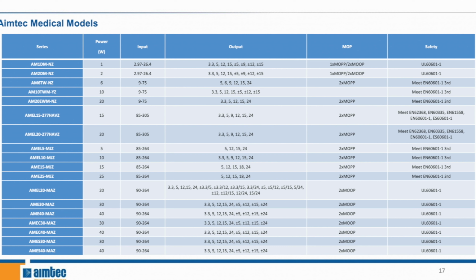And just as a quick note, here is a list of the Aimtec Medical Series. We go from 1 to 20 watts in the DC-DC category, and from 5 to 40 watts in the AC-DC category. And again, it's important to look at the means of protection column to determine whether or not it's MOPP or MOOP. And in the safety column, we can see that the standard, as we mentioned earlier, is 60601-1.